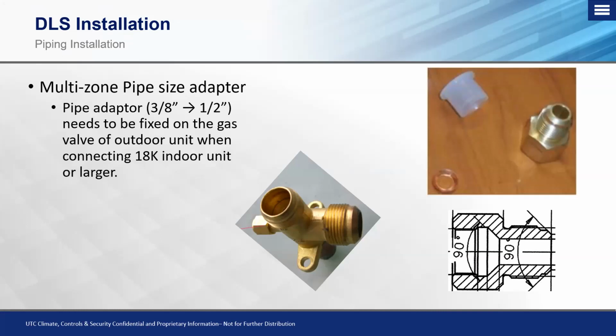Okay, now if you look to the top right on the picture there, you'll see you have your adapter, which hooks on the threads at the outdoor unit. But the most important part is this little copper seal right here, or the ring. When you get this fitting, this part right here that's going to hook on your service valve, you need to take some vacuum pump or refrigeration oil, or you can take an Nylog, and put it on there, insert it in this fitting here so it sits on the little case inside of here, and when you go to tighten down, it creates the seal from this service port onto this fitting.